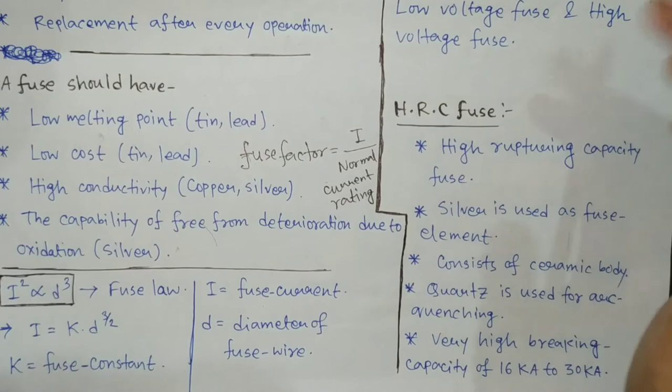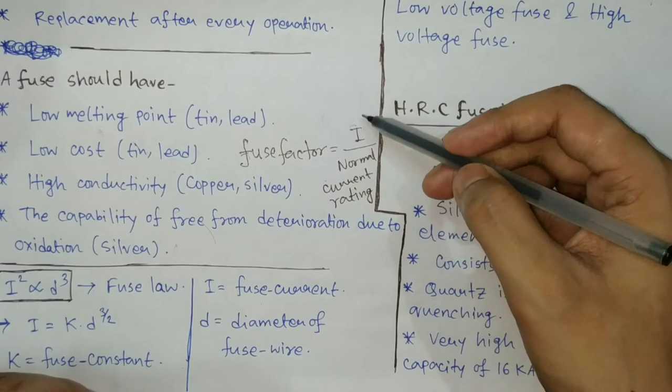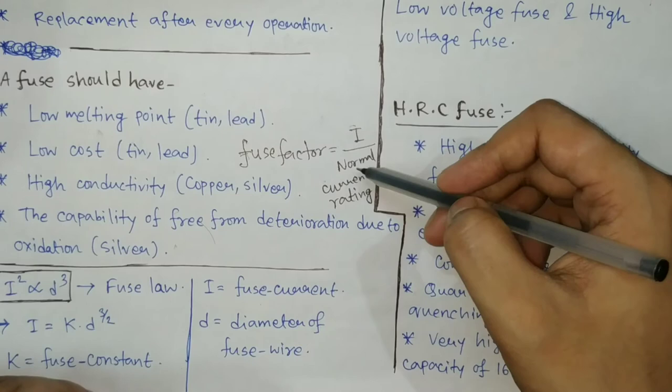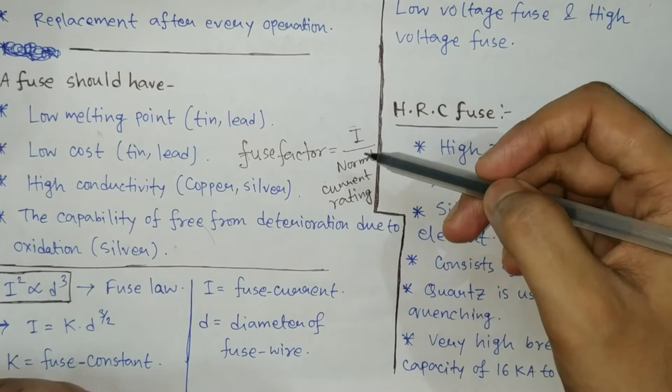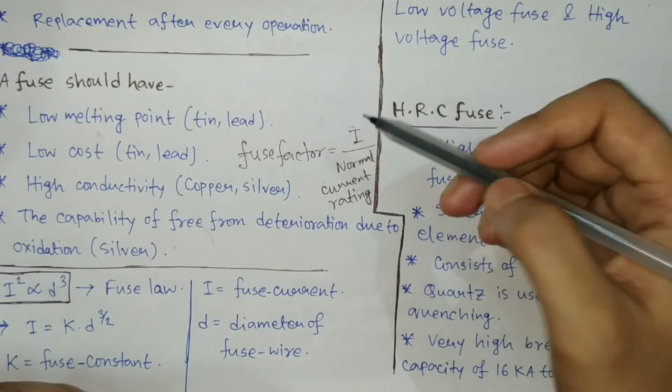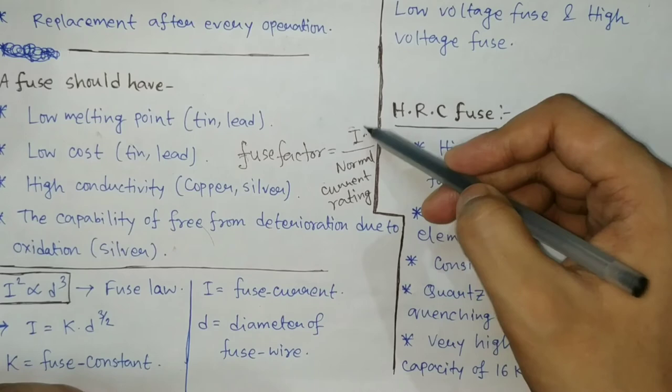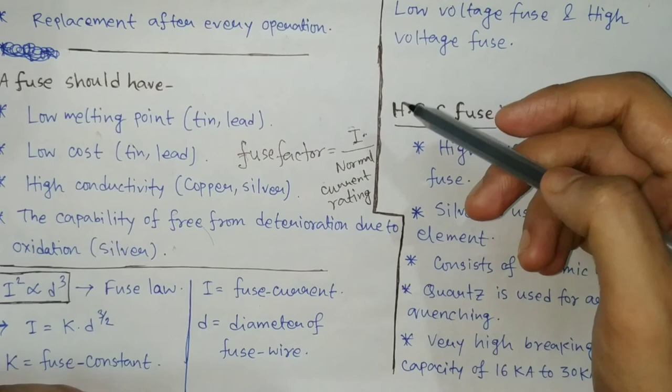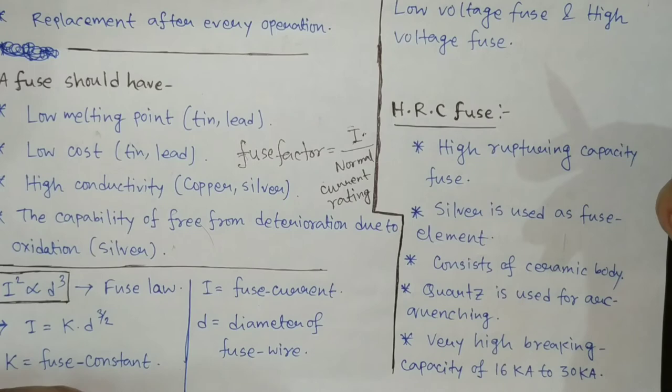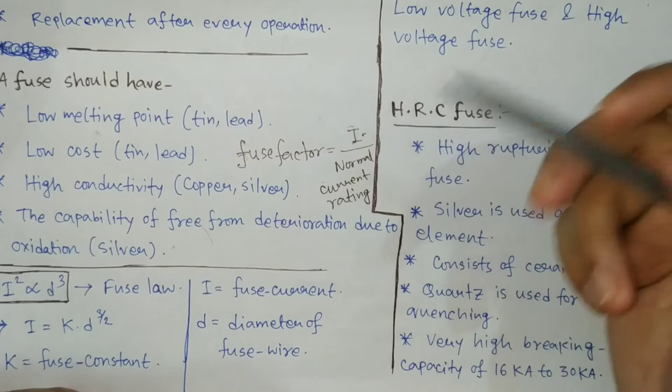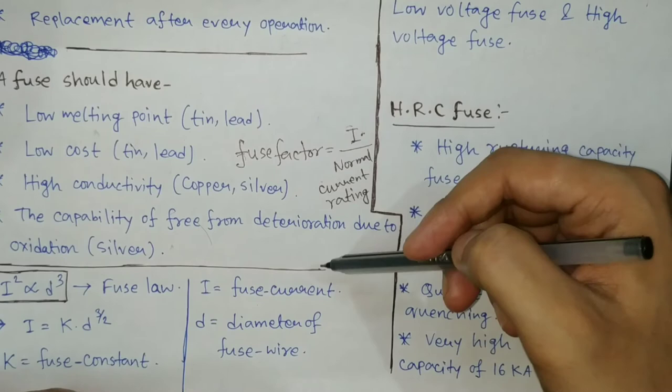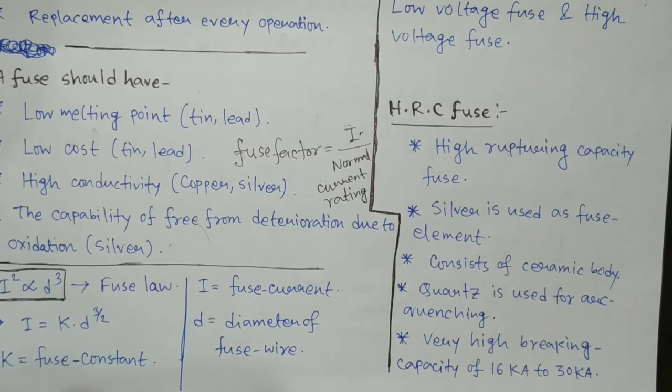Why should fuse factor be high? Suppose it is 1.5. That means I and the normal current are close to each other. That means even if the fuse is carrying a normal current, still there is a chance that the fuse may get overheated or melted. Because I and the normal current are approximately close to each other, there is a chance of deterioration. That is why it is always preferable that fuse factor is as high as possible.